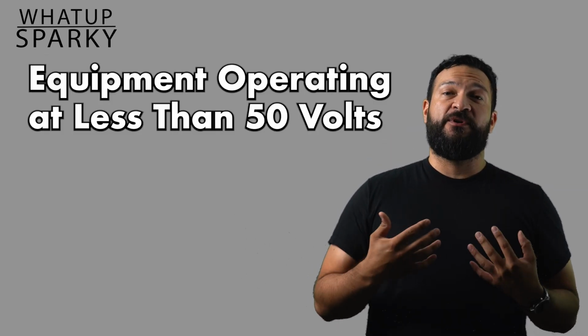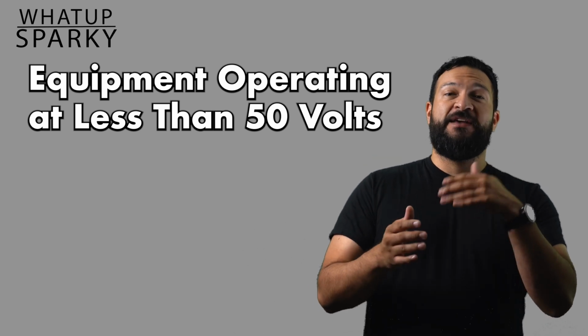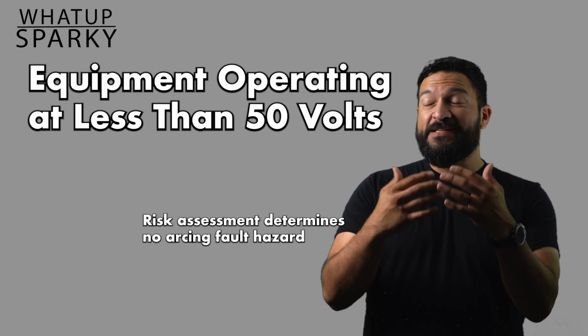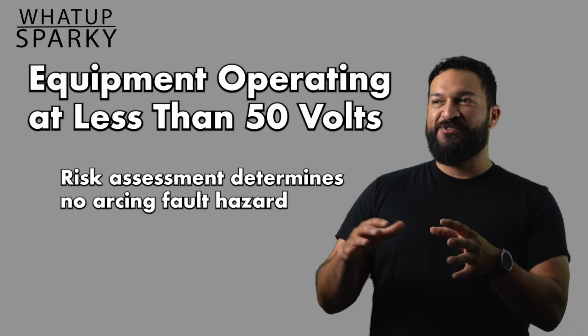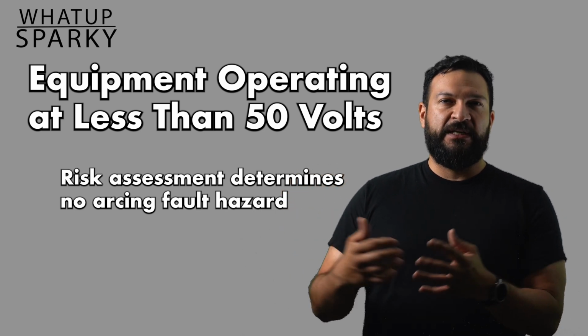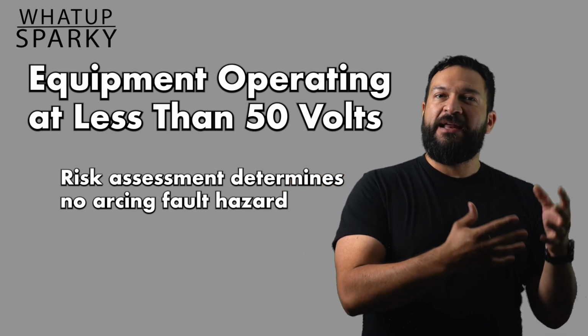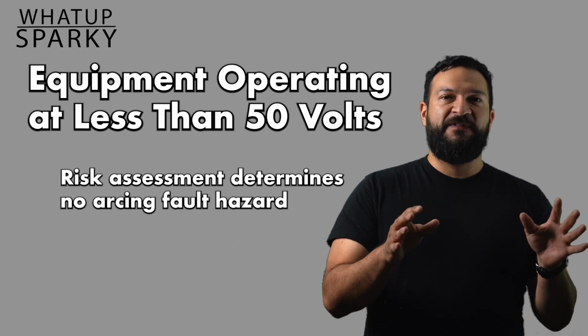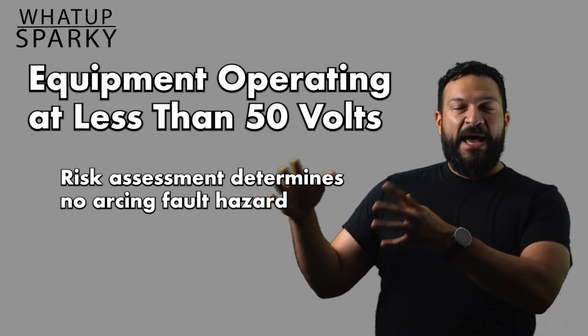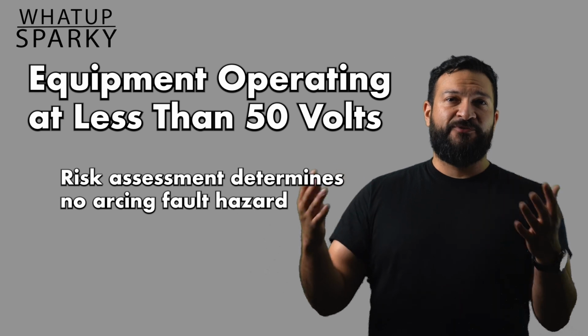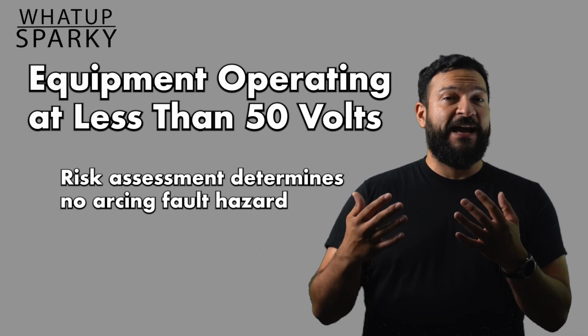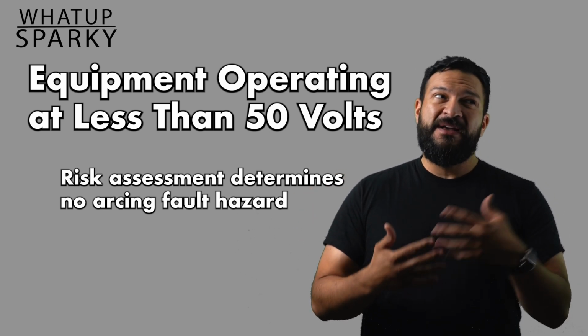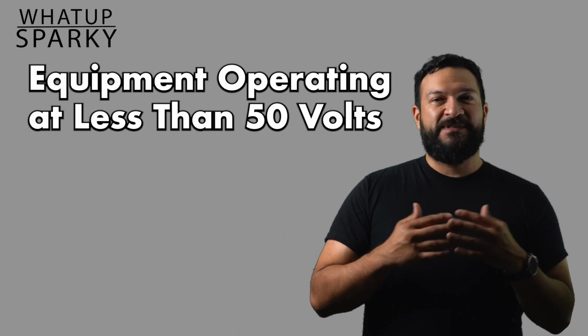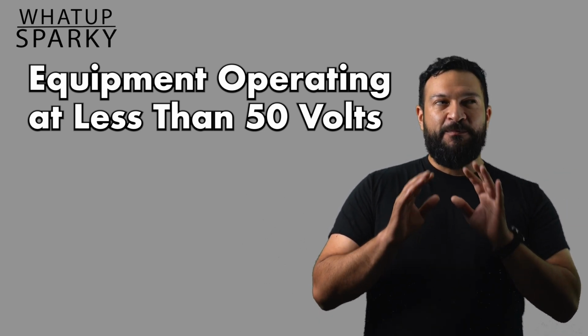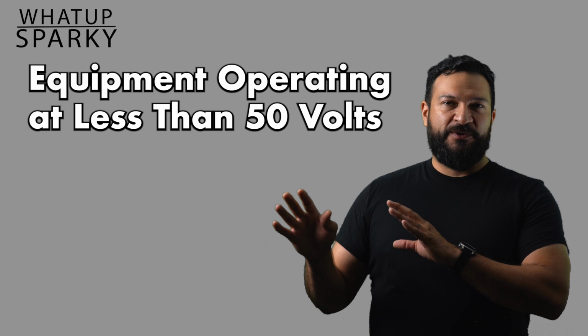And the fourth one is working on equipment that's under 50 volts. Yes, you can work on it if it's under 50 volts and a risk assessment is done that confirms there's no arc flash hazard, essentially. And this, so like landscape lighting or something like that, you're usually gonna be fine. But don't assume that a big battery bank that happens to be under 50 volts, 48 volts, can't blow up in your face, because I've seen it. Is it a shock hazard? Probably almost never, but you're mainly looking for an arc flash potential in those situations.